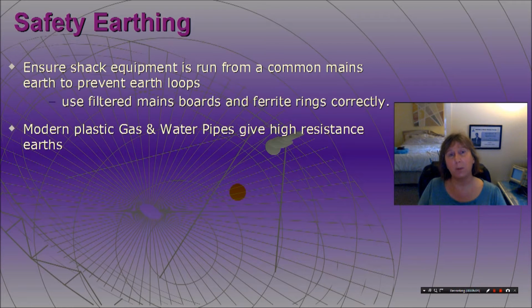I had to point this out for the simple reason that even though you've connected to the metal pipe, which you would hope goes out to the outdoors, major companies now are using plastic pipes for their gas and water pipes, and plastic in itself gives a very high resistance to earth. So your metal pipe from the radiator, which goes just about to the outside of the property, or even within the inside of the property, is then joined on by the plastic. So you're at risk there of inappropriate earthing.